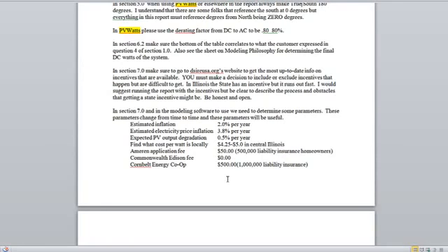So we really want to have a good value that everybody knows where that number comes from. I would state that historically the 2.0 plus the 3.8 for 5.8 is probably a little low. Over historical trends, some of you will say, well, regionally we're doing less. I can't predict in the crystal ball. I'm going to run with 5.8. I'm going to be a little conservative. If the client goes forward with their renewable energy project and they end up saving more money than you calculated, they're going to be much happier than with the rate of return and the cost analysis based on too low of an estimate of increase. We don't know what's going to happen, but those are some numbers that I want you to follow in my class.